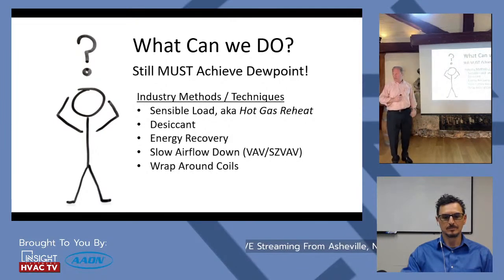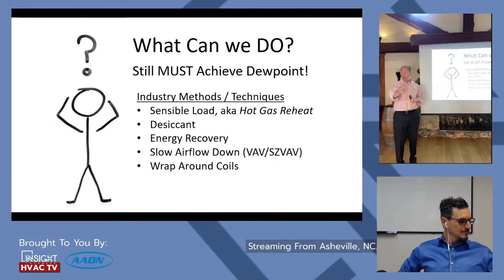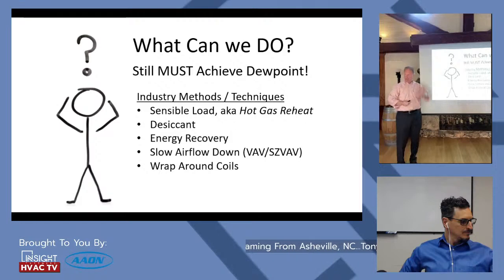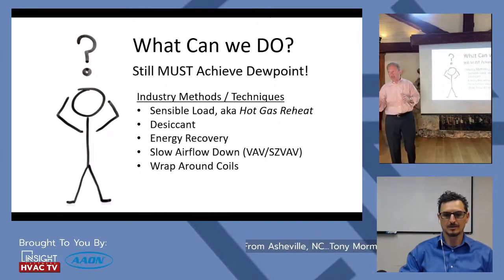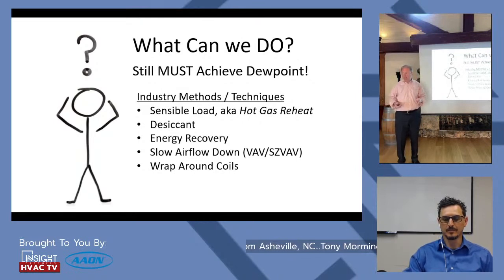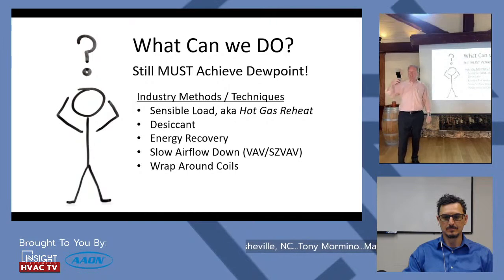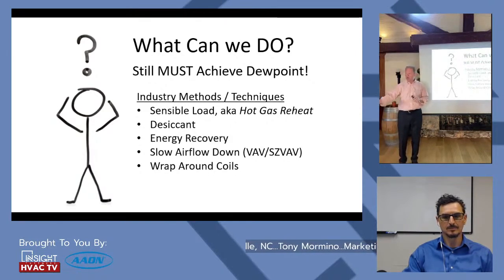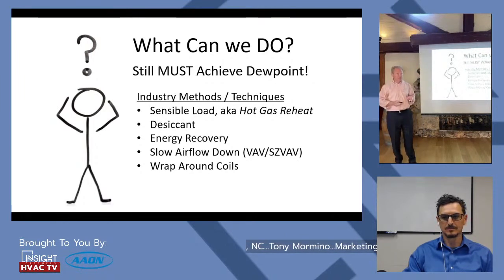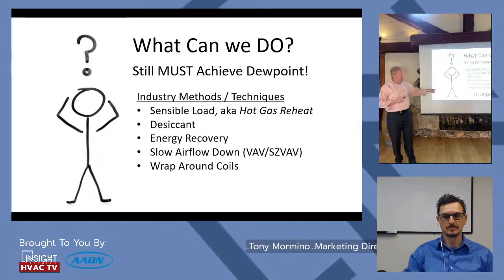Wraparound coils are another technique — you pre-treat some of the outside air, drop out some moisture, run it through the standard DX system to get down to 55°F, then warm it back up. Your supply temperature is higher, so you have less sensible capacity — which is sometimes exactly what the application needs. There are probably 10 solutions to every HVAC application, and you choose based on cost, energy profile, and local power rates. Design differs between the high-power-cost Northeast, islands with expensive power, or areas like here with good power rates.